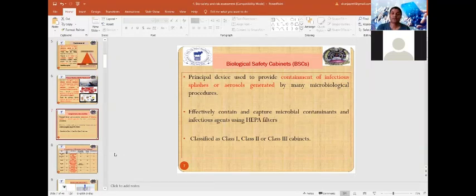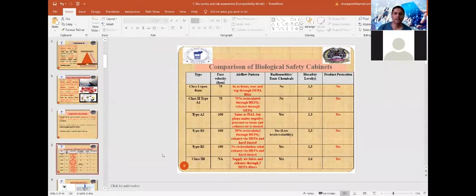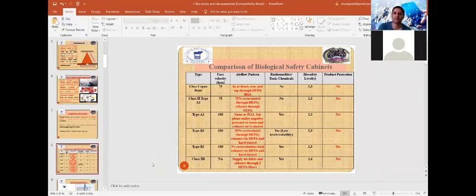Most bacterial or viral organisms are captured by the HEPA or ULPA filters fitted in biological safety cabinets. Based on the capability and mode of action of these equipments, biosafety cabinets are classified into Class 1, Class 2, or Class 3. The classes differ in airflow patterns, capacity to handle radionuclides or toxic chemicals, biosafety level use, and protection level.